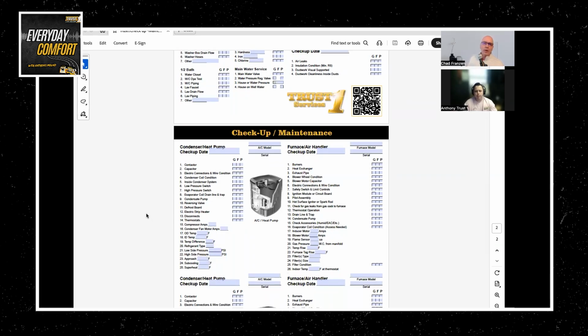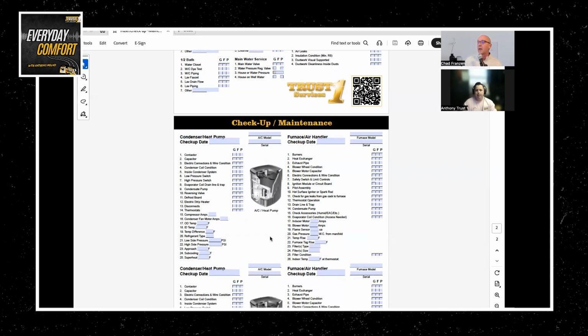So let's start with furnaces. When you check things like burners, heat exchanger, and flame sensor, what are you actually looking for? Yeah, so the heat exchanger contains the flame and the combustion. So we're looking for cracks or any damage inside the heat exchanger itself, because if there is, then you could emit carbon monoxide into the home. Flame sensor and igniters, we're actually checking power or continuity across those electrical components and making sure there's proper power or continuity.